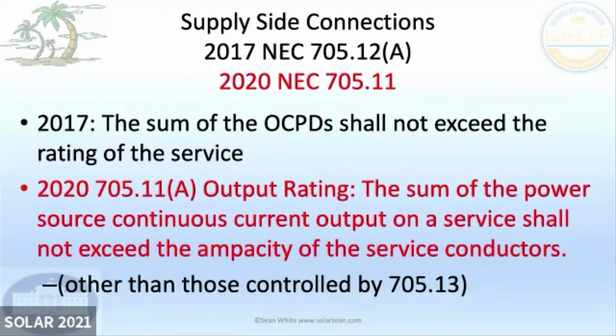A supply side connection is where you're connecting between the meter and the main breaker, usually the main service disconnect, the first overcurrent protection device. So you're over there where things are not protected, where the utility is. You're adding your little insignificant amount of power to that giant, great nuclear power plant or whatever else is out there. It's not like you're adding extra power to your loads, because your loads are already protected with the main breaker. When we do a load side connection, we're adding extra power besides what that main breaker can supply, so it's more of a big deal there.